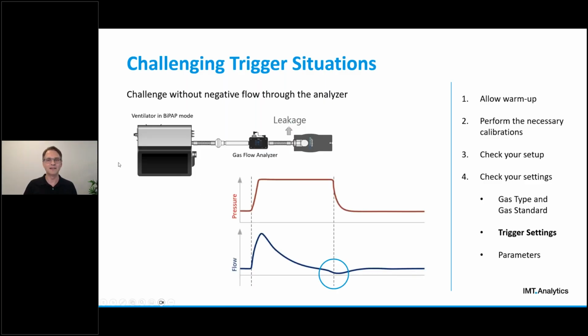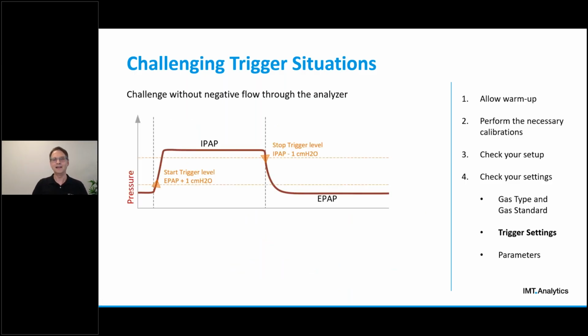A typical resulting flow waveform in such an application is also not a suitable trigger signal due to the lack of a steep falling edge at the end of the inspiration phase. On the other hand, the pressure waveform looks pretty good as a trigger signal, as it features steep rising and falling signal edges at the beginning and the end of the inspiration phase. So let's have a look at the pressure curve and see how we would set the trigger settings here.